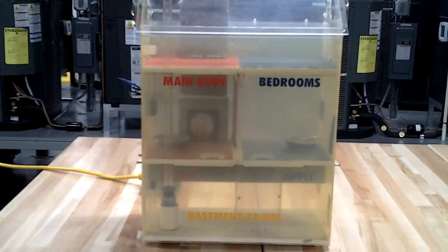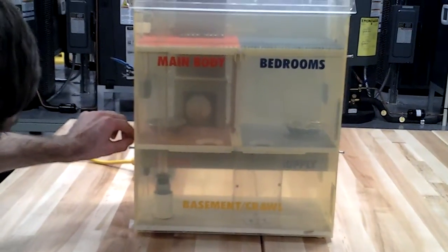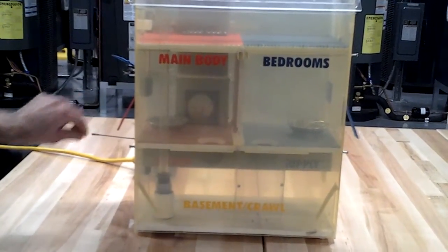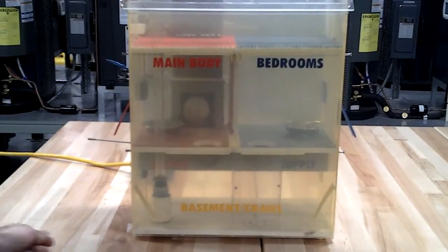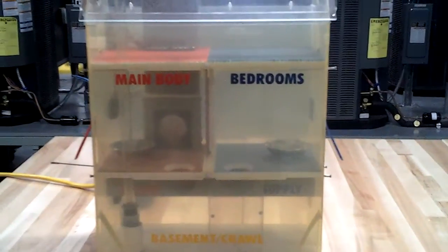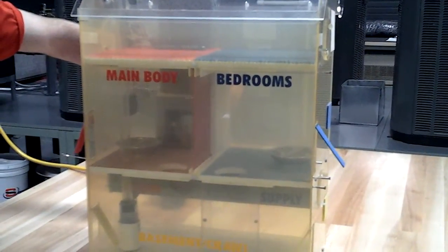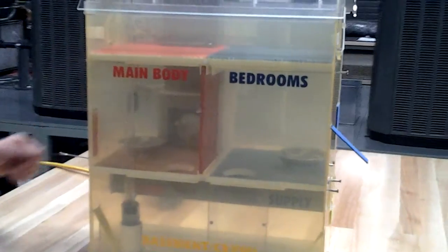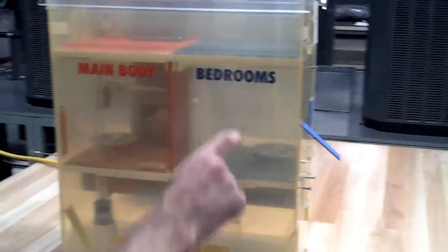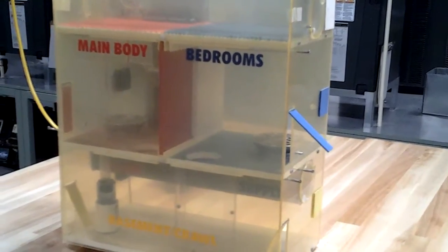A return air duct leak within the confines of the house will then, when introduced, introduce an excessively negative pressure in the basement or crawl space of the house. That negative pressure then wants to equalize, and in turn it goes positive in the upper levels of the house, thus exfiltrating through the walls there. If you then close off a partition separating the two rooms from one another, then the negative pressure from the one side gets forced to the return or the supply side of the ductwork and exfiltrates the house.